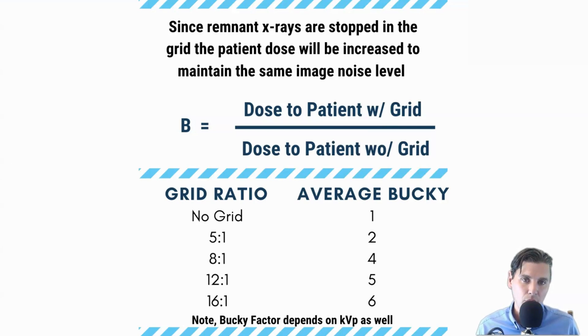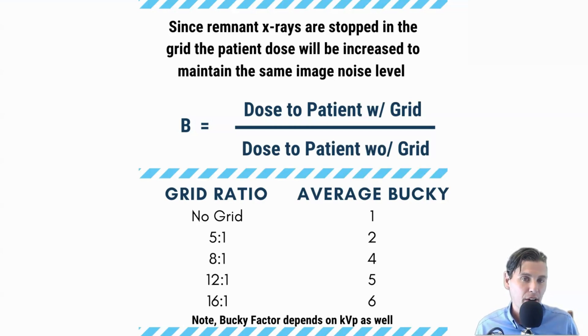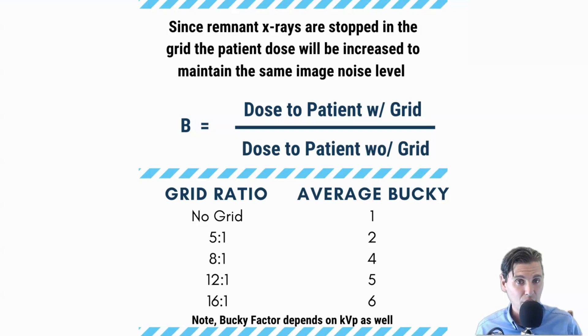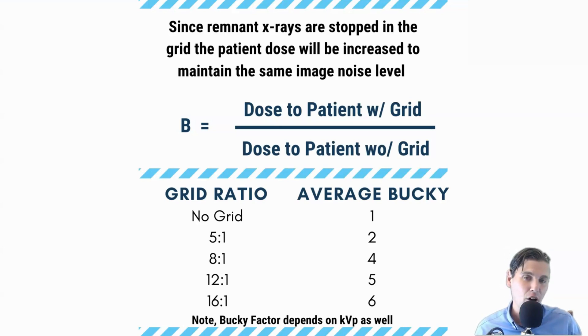The Bucky Factor will also depend on the kVp, but these are average values. For a 5:1 grid, you're going to need about a factor of 2 more in terms of the mA on the system. You'll have to take tube loading into consideration when choosing scatter grids. The contrast improvement factor will really help you identify lesions better, but you have to weigh that against the Bucky Factor — the increase in dose because not all photons make it all the way through.